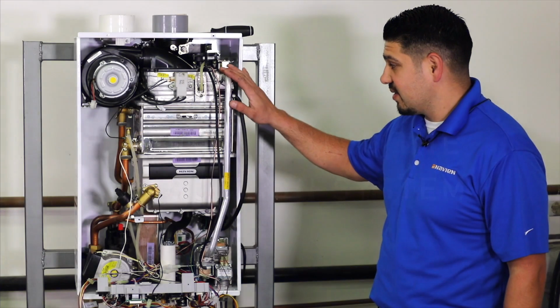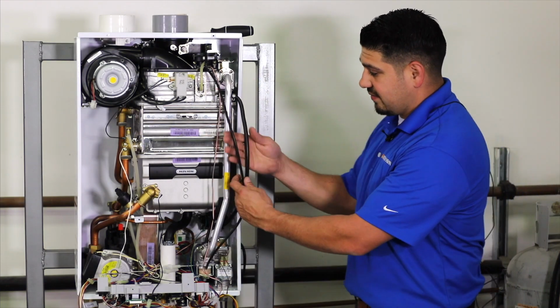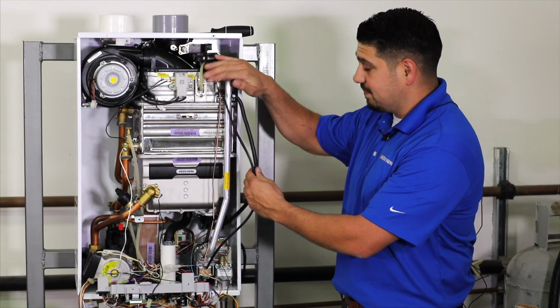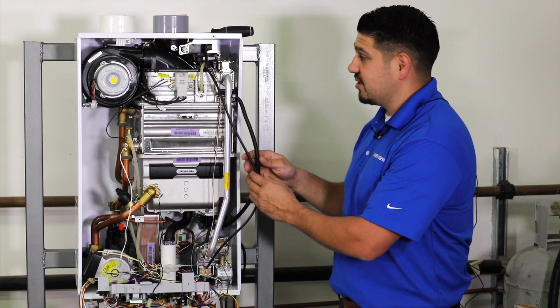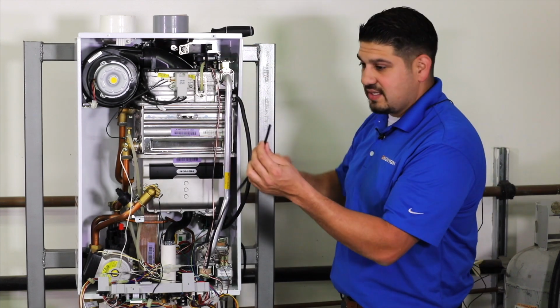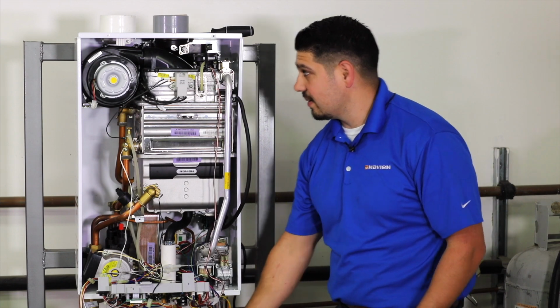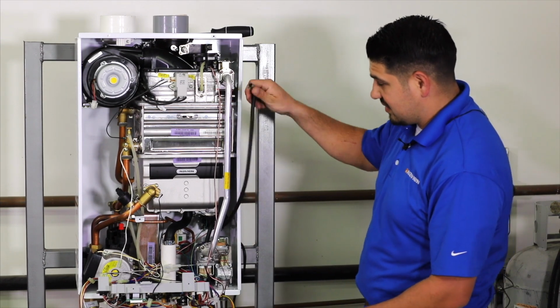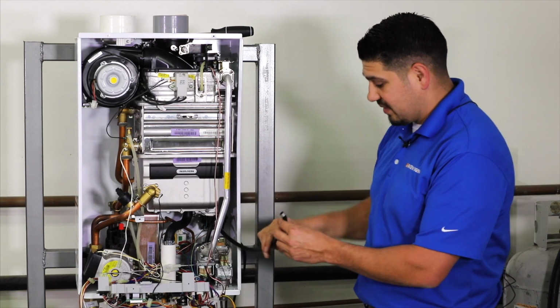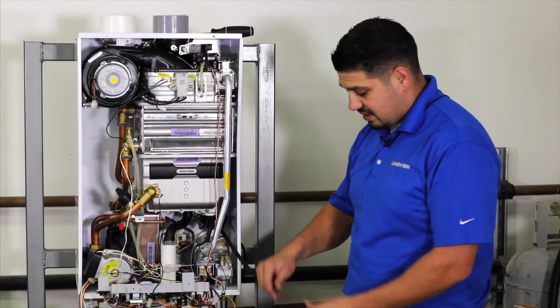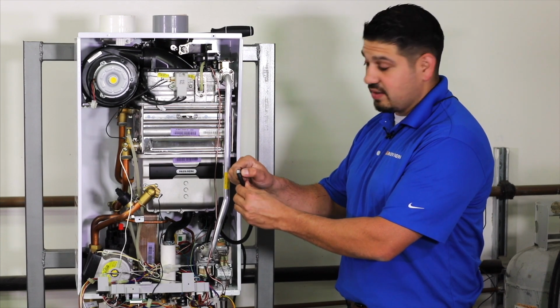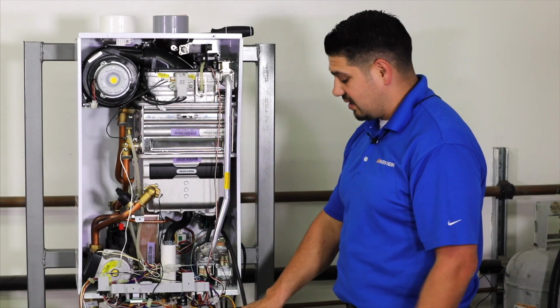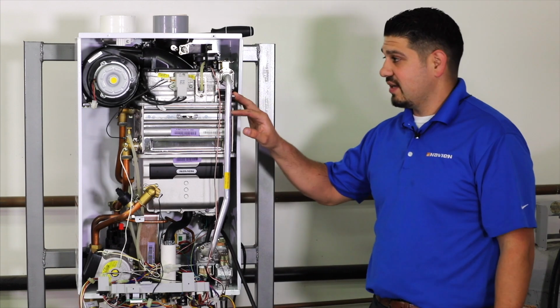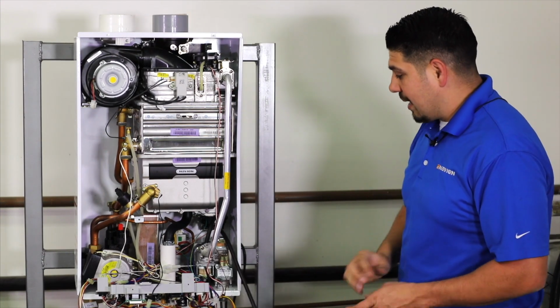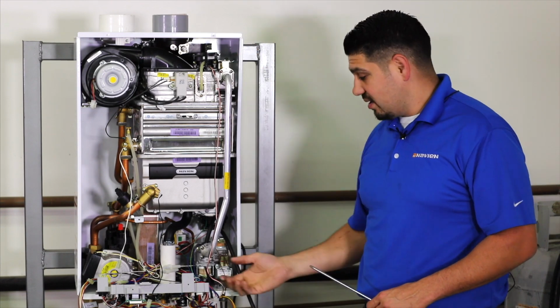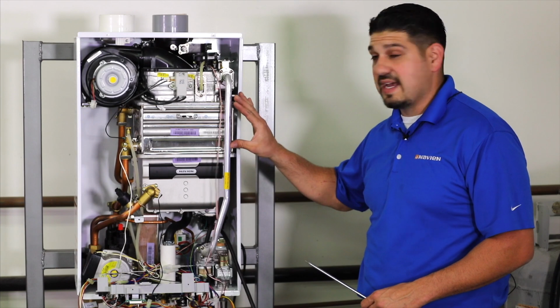We're going to work on our combustion system here. So we've got a series of hoses we're going to get disconnected, and we're going to take off our gas tube here. You've got this skinny tube; you can just let that hang there. And then right here on the side of this big tube, your gas line, I'm going to take that off. It does have a hose clamp. You could use channel locks or some kind of pliers to remove that, but usually you can get it with your hands. Then you've got a series of 4 screws on the top and another series of 4 screws on the bottom. You're going to get those off, and this gas tube should just pop right off.